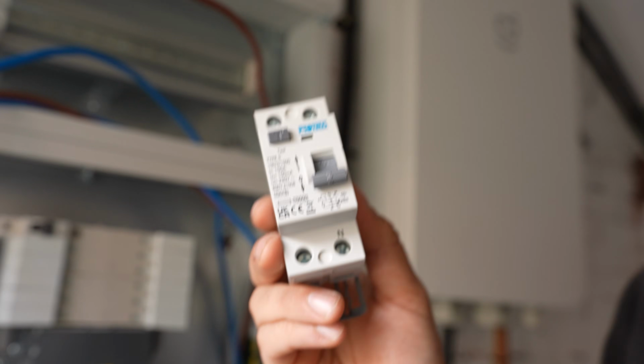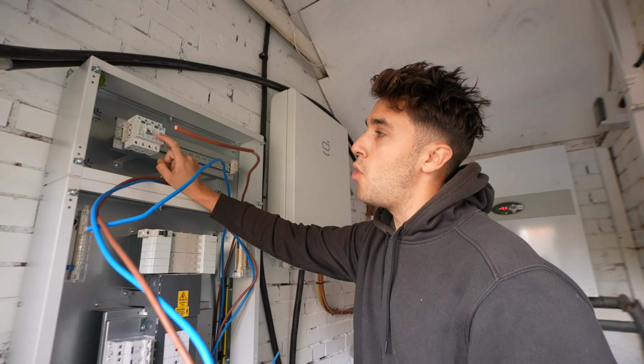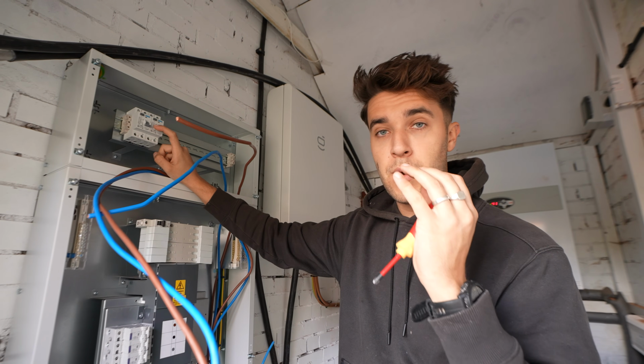Now, the reason why we have 100 milliamp is for a similar reason. We want to achieve discrimination. All of the devices within the house are going to be 30 milliamp devices. This is going to be 100 milliamps to achieve, again, that level of discrimination, because we want the ones within the property to trip before this one, so that they're not having to walk in here to reset every time. Now, there's a reason why we use 100 milliamp when we're using an earth rod.